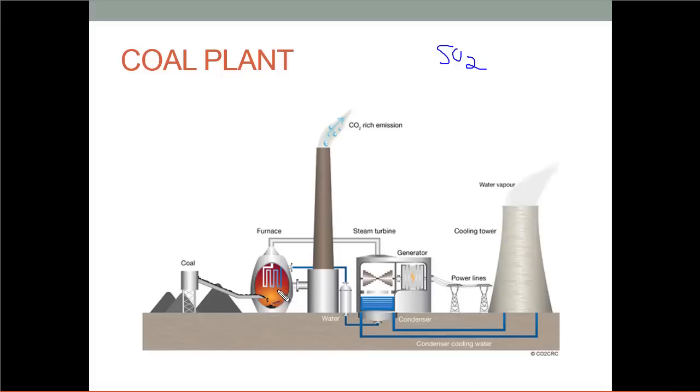So the emissions of the power plant are an important thing. And we're interested in SO2 emissions, which is from sulfur in the fuel, right? And SO2 makes acid rain. And I mentioned in the very beginning of this lecture that I worked for the power company and did emissions monitoring. And the CEMS, the continuous emissions monitoring systems, what we do is we actually put a little probe in the stack here, and we have a little shack down at the bottom with some computers in it and some analyzers, and we continuously measure what's coming out of this smokestack.